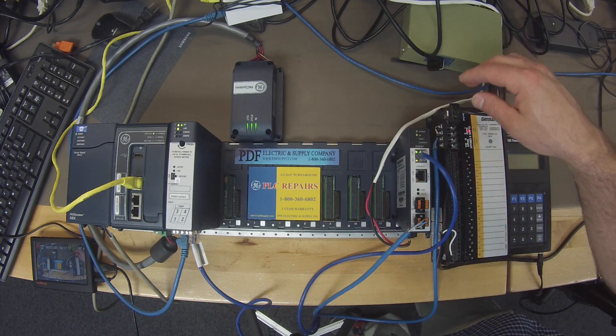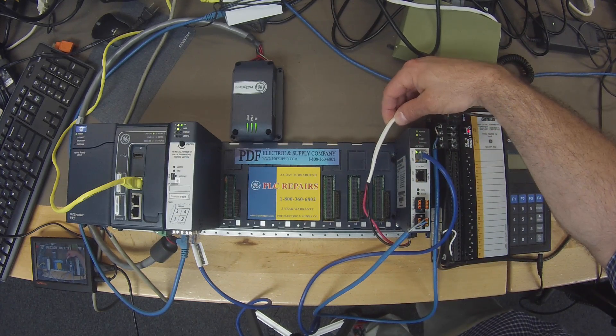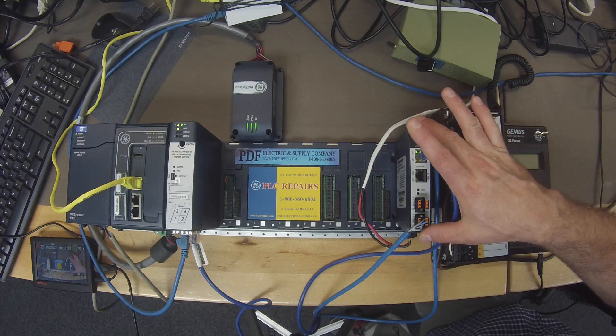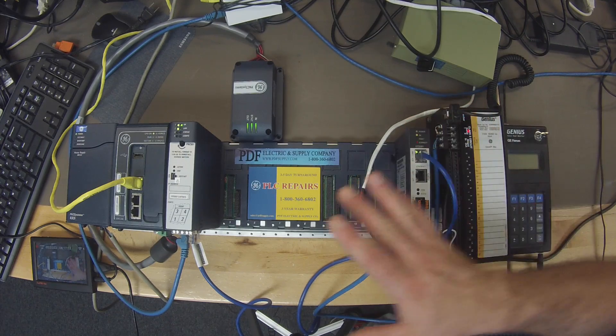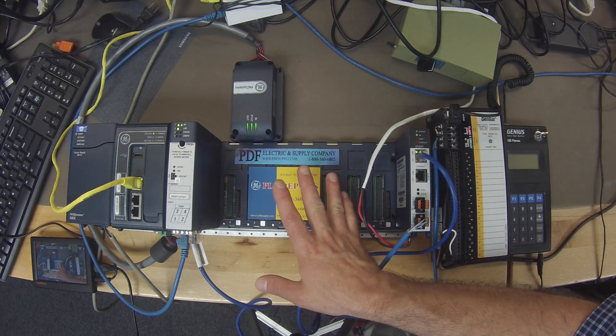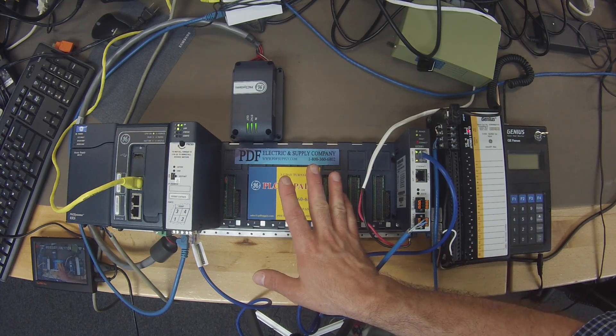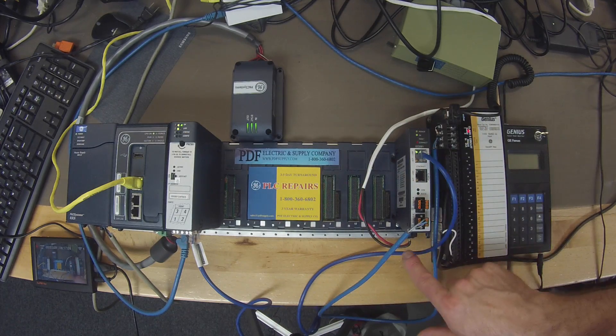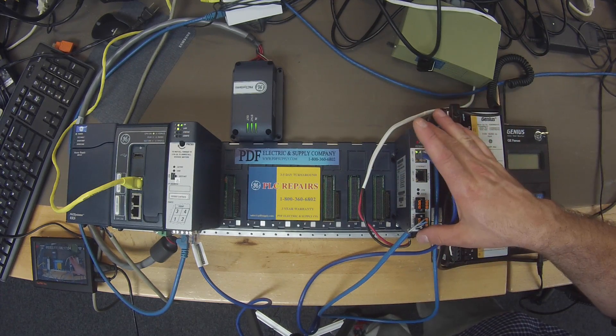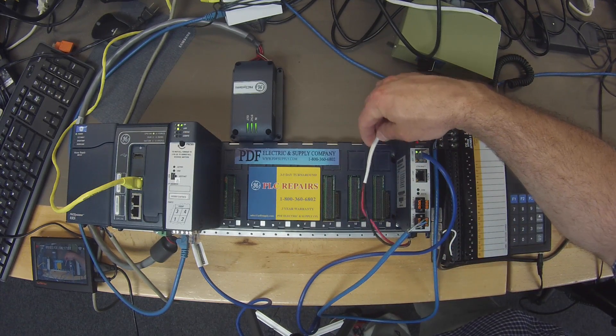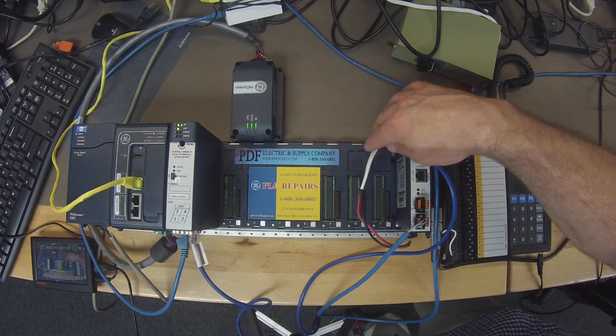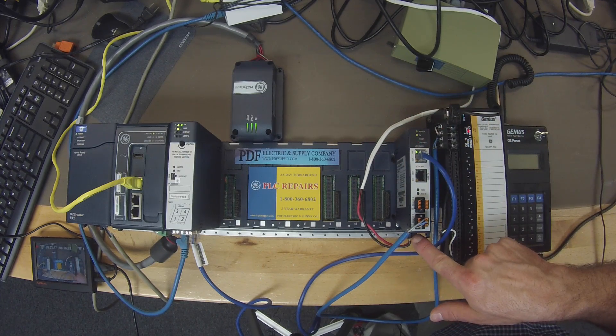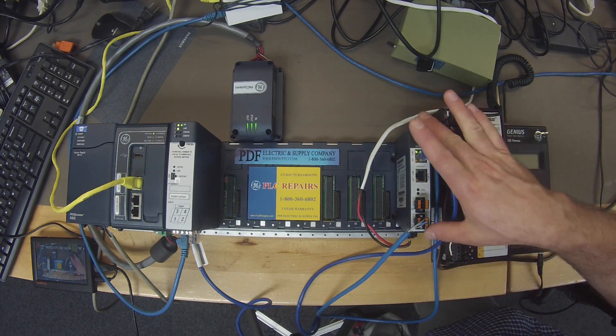So a few wires here. Then last but not least, in order to power up this device, since it's not actually connected to the chassis, you will need an external 24 volt DC power supply. This wire is going to my 24 volt DC power supply and to the bottom of the module where it's connected.